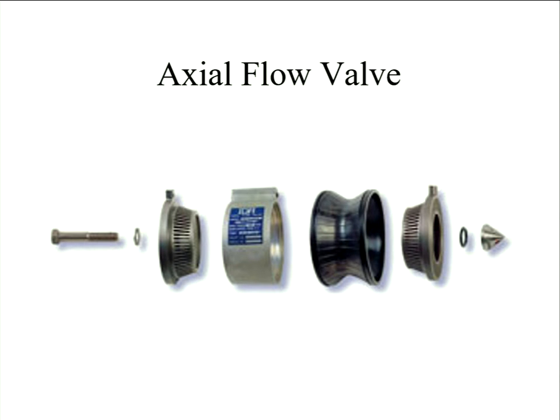So if you look at say a distribution governor, it might just have two streams in parallel with only one valve in each, whereas at the higher pressure, you've typically got two controlling ones there. So that's the one that's normally operating. If that fails, this one's got a slightly higher set point, so pressure rises, this starts to control. If that fails, this will close down, but there's an equivalent parallel stream behind, so you've got redundancy against failures open and failures closed.